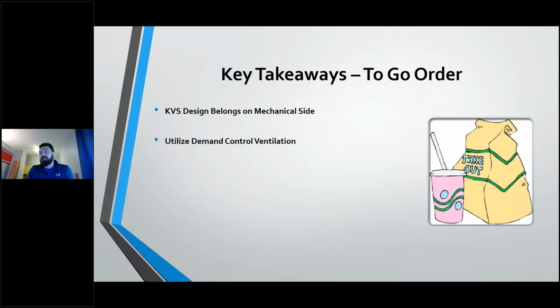Utilize demand control ventilation whenever possible. The price point between the constant volume and the variable volume cost, again, across the board, has come much closer, and the overall payback is extremely good across the board. And it's just a better energy consumption item. So DOAS, heated makeup air, cooling makeup air, whatever the case may be, apply it when necessary.